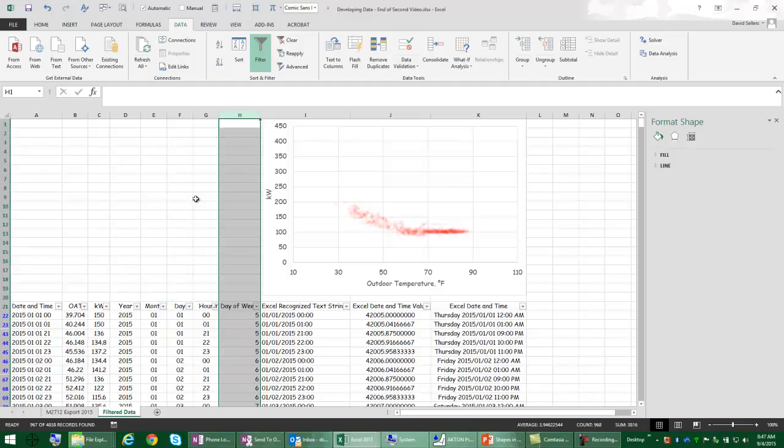Okay, now I seem to have a pattern, and so what this is basically the base load consumption pattern for this facility. And so I could actually calculate how much energy the facility uses as base load if I could come up with the equation for that data set. Which, there's mathematical ways to do that you may or may not have learned at some point in your career. But Excel makes that pretty easy.